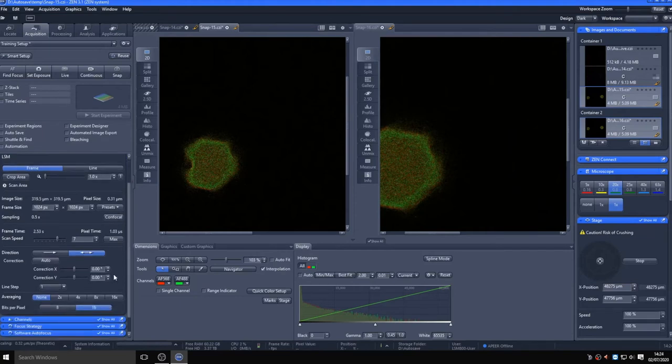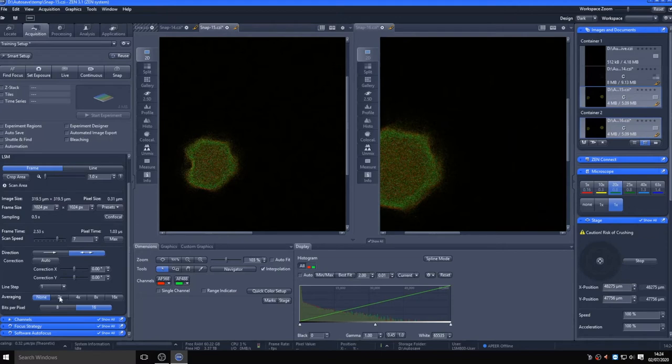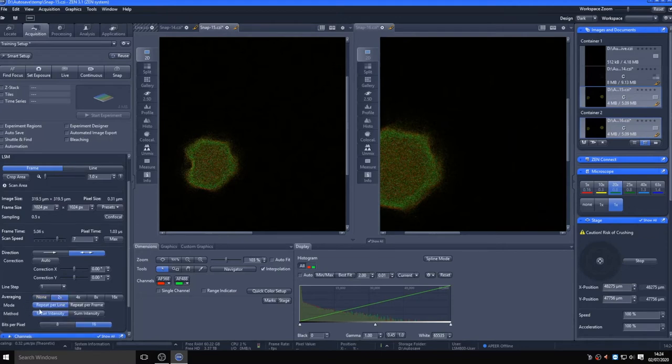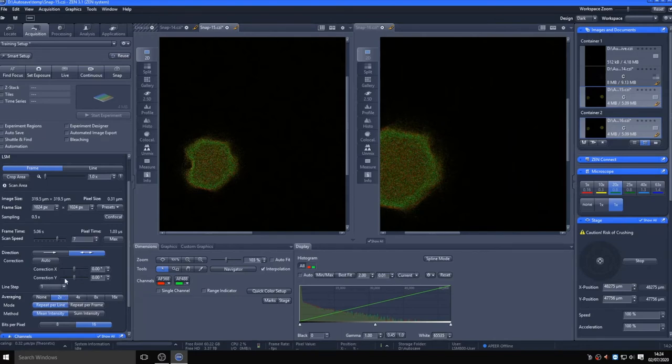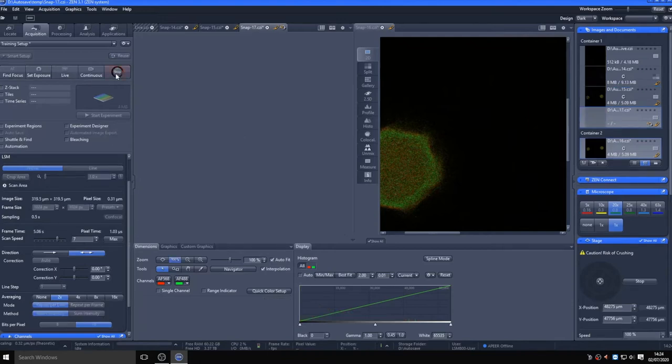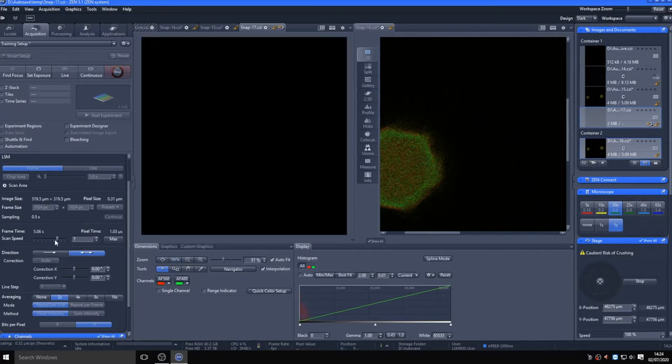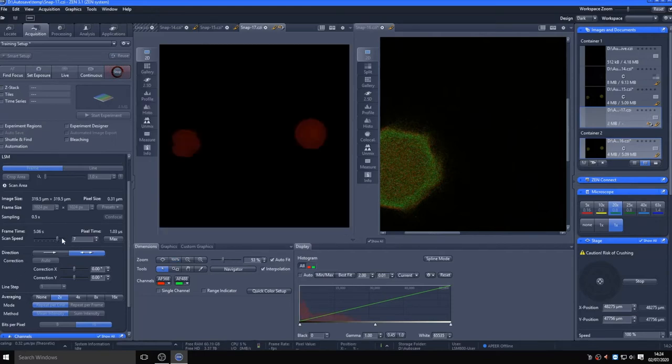An alternative way of achieving this would be to use the averaging option, which scans the same pixel multiple times on a per-line or per-frame basis rather than imaging each pixel for longer in one pass. This can be less damaging to your fluorophore if it is prone to being photobleached, but is no good for any samples with movement in them, as this will introduce blur, since there is a significant gap between lines or frames. Of course, it is possible to use both at once to obtain a better image.